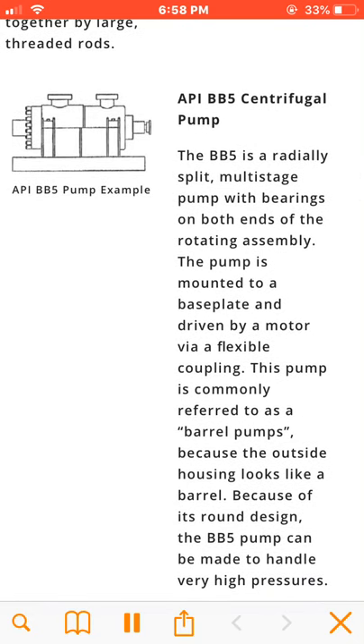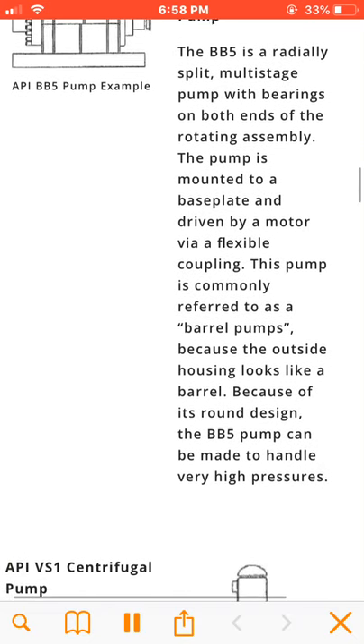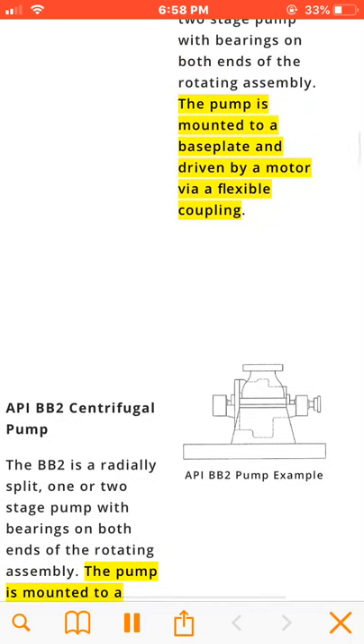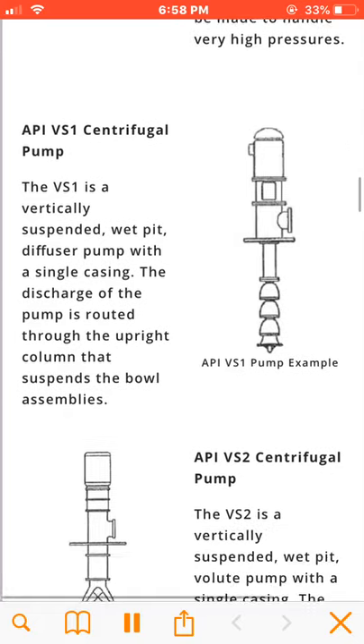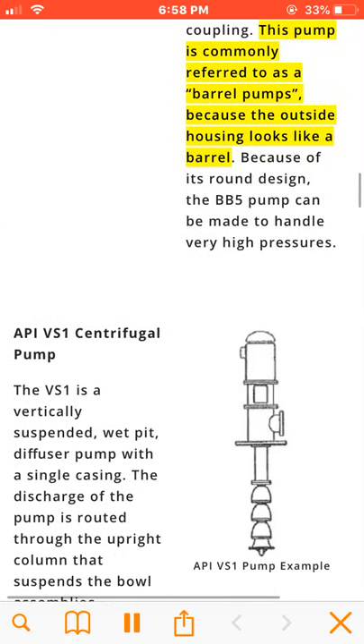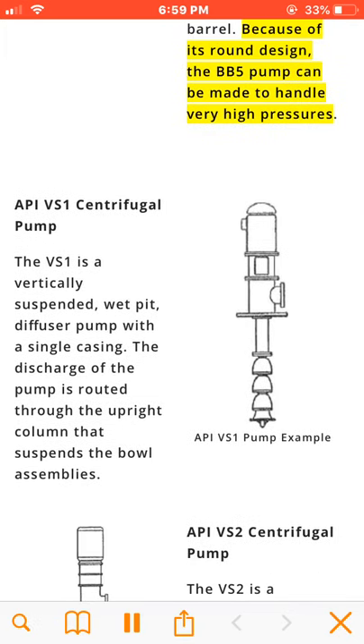The BB5 is a radially split, multistage pump with bearings on both ends of the rotating assembly. The pump is mounted to a baseplate and driven by a motor via a flexible coupling. This pump is commonly referred to as a barrel pump because the outside housing looks like a barrel. Because of its round design, the BB5 pump can be made to handle very high pressures.